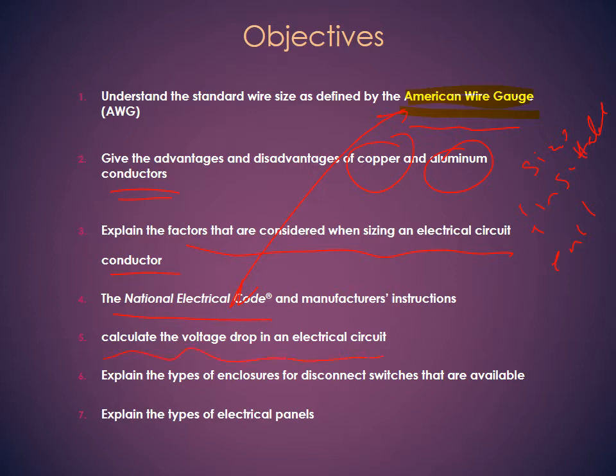We also would like to calculate the voltage drop. What is voltage drop and why do we have to care about that? We will talk about that in a second. Explain the type of enclosures. By enclosure we mean conduits, junction boxes, control panels, covers, all these enclosures for wires, because we don't want to see wires exposed. Wires should not be exposed, because then they are subject to a lot of the weather elements, the possibility of being disconnected, rodents, or anything else.